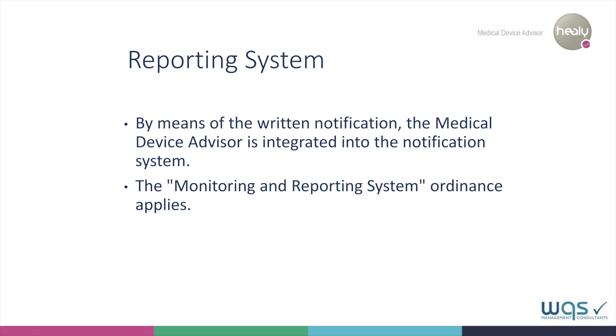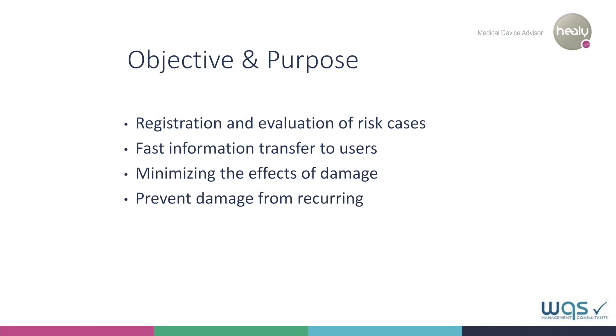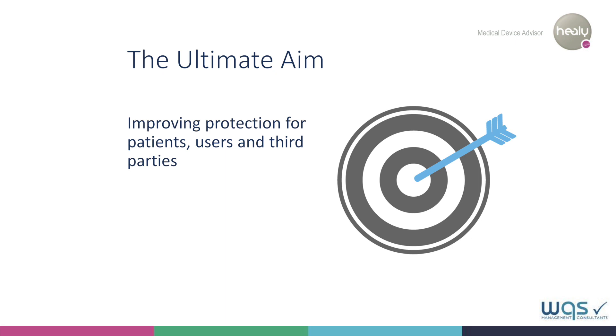The reporting system that you will be a part of follows the guidelines regarding the monitoring and reporting system. This system entails: Directive 93/42/EEC, Protective Clause Information on Occurrences After Entering the Market, Medical Device Safety Plan Ordinance, German Medical Devices Act, Monitoring and Risk Protection Forms and Record Sheets, and Quality Management System. The point of all this is ensuring that by recording risk cases, important information can quickly be passed on to other users of the medical device, thus keeping any damage as low as possible and, above all, preventing damage. It's all about the user — their protection is the ultimate goal.